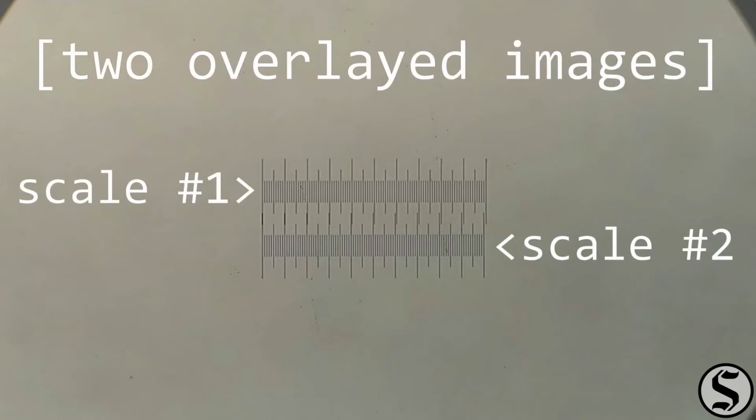So here's a perfect example. These are images taken through 10x optics from the same supplier. The hardware looks very slightly different, so I'm thinking they might come from different manufacturers selling to the same supplier, but they're branded the same, and the results are close, but not identical. So clearly they can't both be a perfect 10x. And again, that's totally fine. I just measure the scale bar for the optics that I'm using.